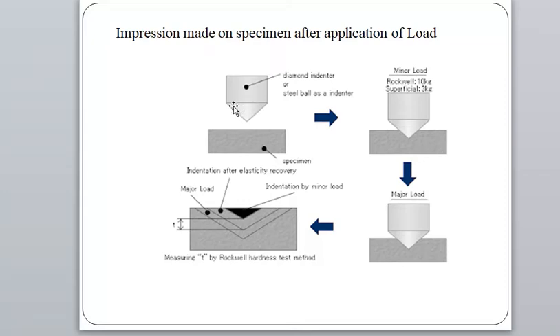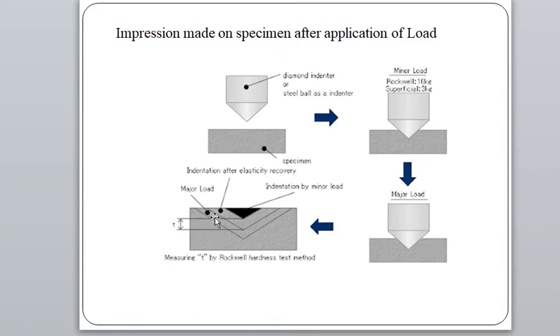The final step is to calculate the average of all trial readings to get the final hardness value. The diagram shows the impression made on the specimen: when minor load is applied, there is initial penetration shown by the black region. When major load is applied, there is deeper penetration, and the depth denoted by 't' represents the depth of penetration after major load application.